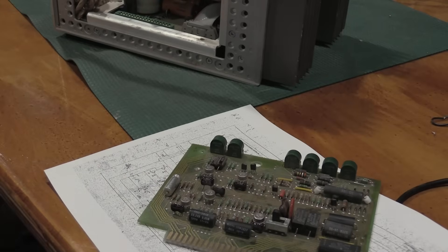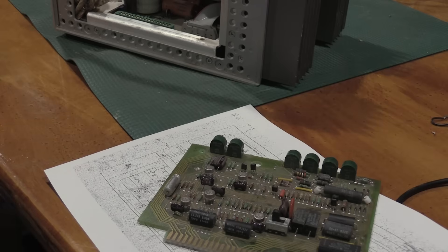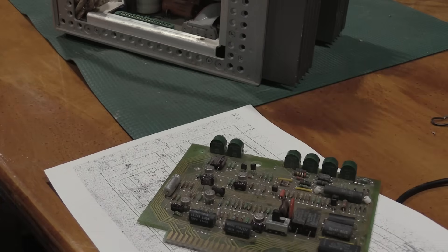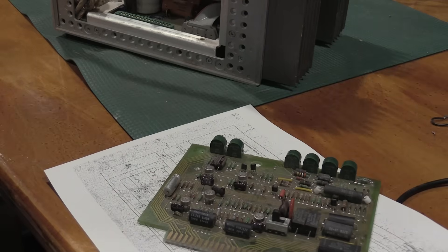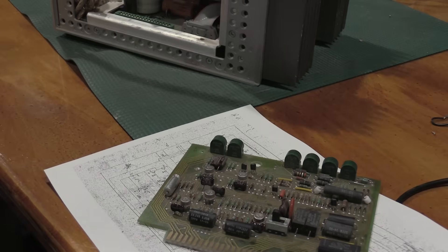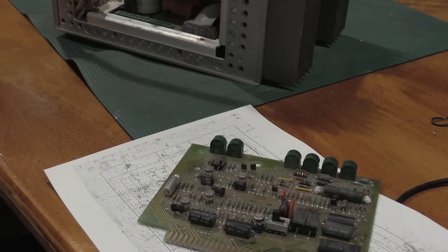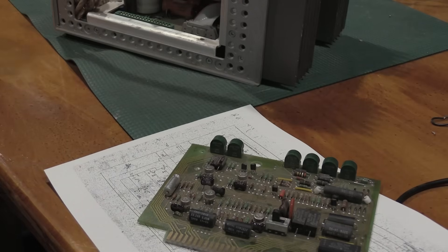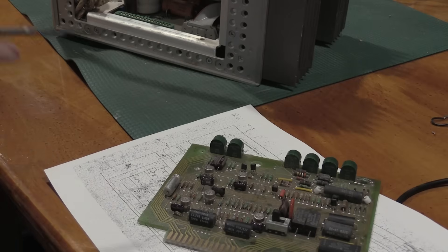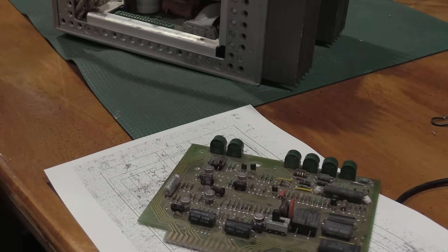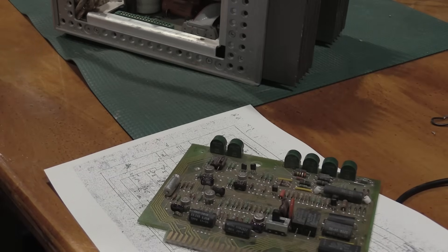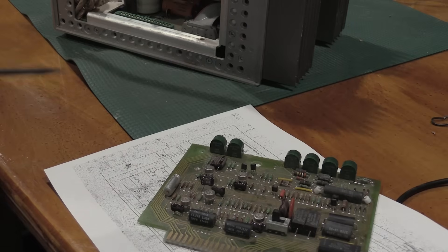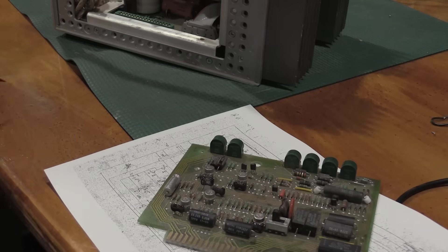So at this point, here's what I think happened. Given that we had some damage in this power supply with that resistor, and I actually now know what that resistor and relay are doing, and we have some parts that are missing, I think I'm starting to figure out a story of what's happened to this poor power supply. There's two models of this, the 6826 and the 6827. I think this is a control board for the 6827 that somehow found its way into the 6826. They're very similar boards, but there are some differences. There are some resistor values that are different, and there are some other things that are different between the two boards. So the units are not 100% interchangeable. So I think this is a 27 control board in a 26 chassis.